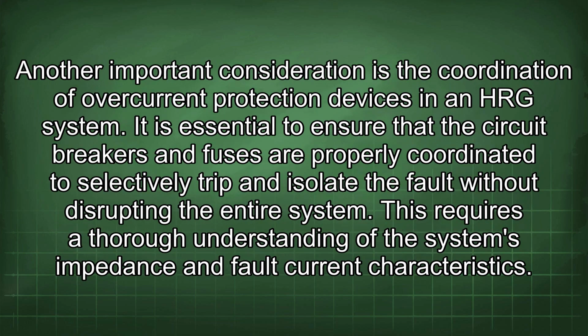Another important consideration is the coordination of overcurrent protection devices in an HRG system. It is essential to ensure that the circuit breakers and fuses are properly coordinated to selectively trip and isolate the fault without disrupting the entire system. This requires a thorough understanding of the system's impedance and fault current characteristics.